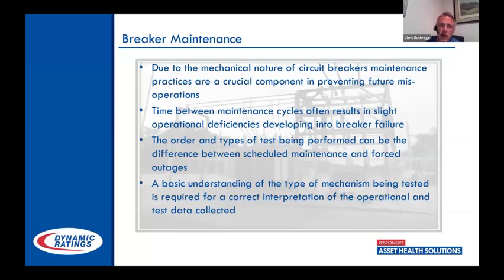When I worked at the utility, I spent a lot of time on transformers. We did all our commissioning, testing, and replacements, and started looking into why things fail. When you start looking at transformer failures, everybody's aware you have a breaker that doesn't open. We had a couple of those where there weren't breaker fail schemes in place, and a six-minute three-phase fault goes to a piece of equipment and burns the station down.